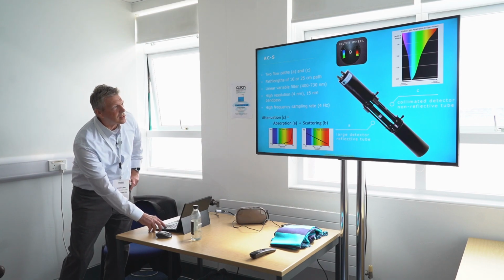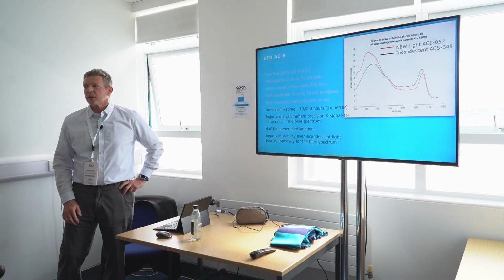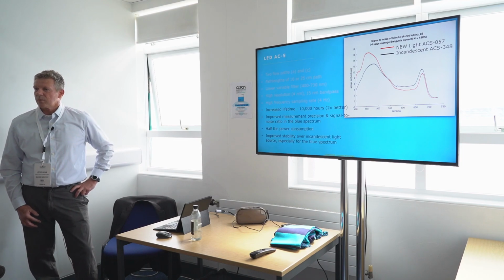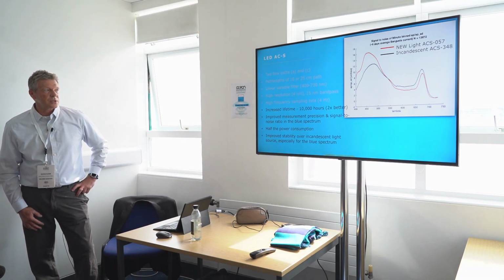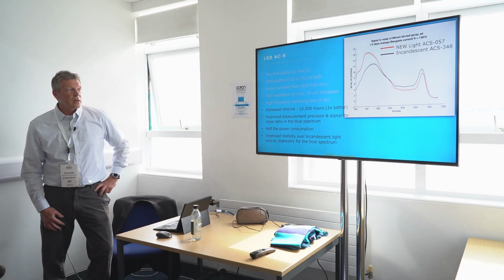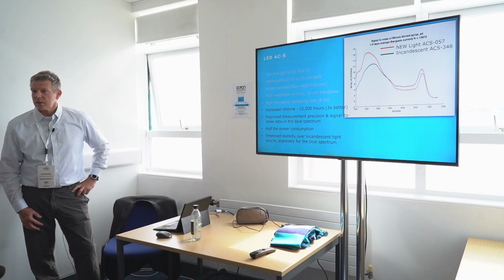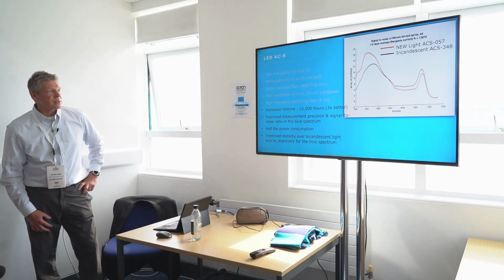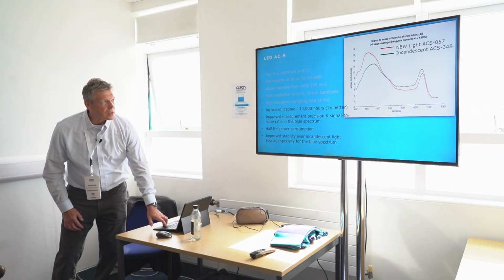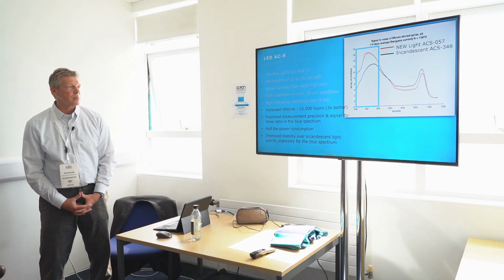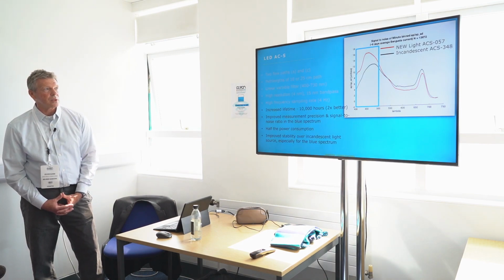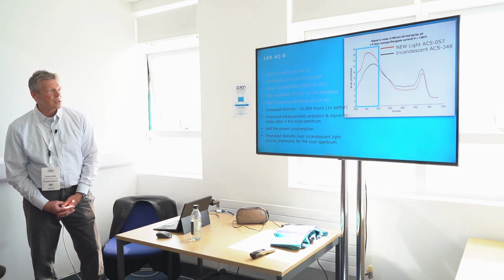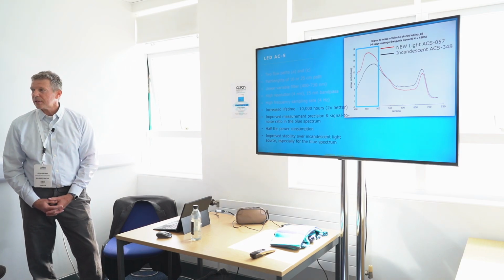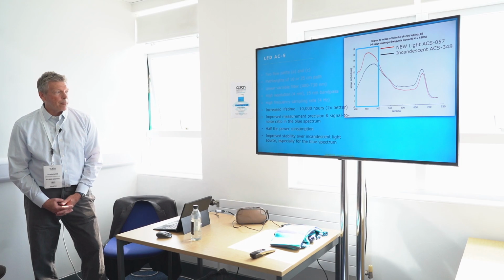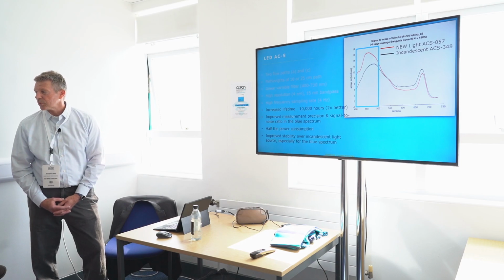The improvement there was really about replacing the incandescent light source with a white light LED source. There are a few advantages to that. It increases the lifetime by about a factor of 2, to about 10,000 hours. It also improves the signal to noise ratio, especially in the blue part of the spectrum. That's a huge advantage compared to the original incandescent light source. On top of that, LEDs typically have lower power consumption, and they age slower, especially in the blue part of the spectrum.